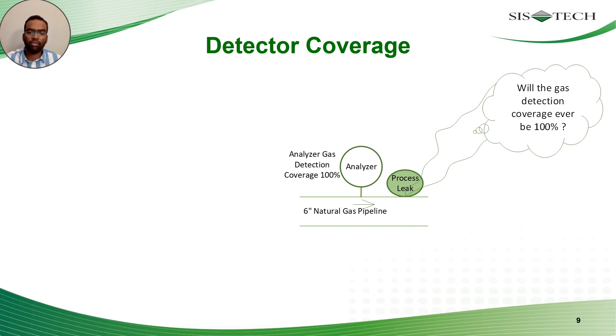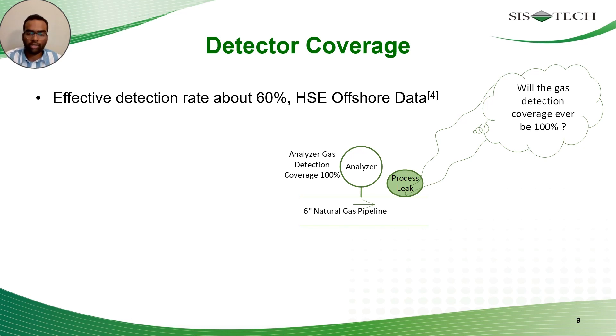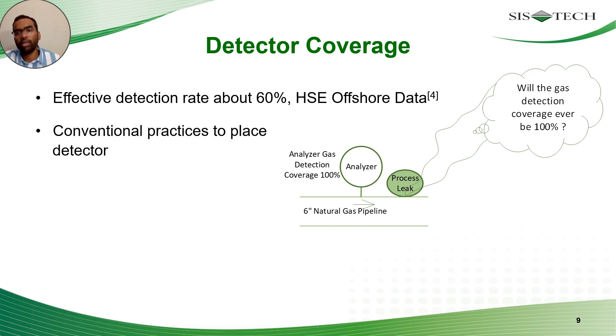Detector coverage is critical to overall FGS effectiveness. An analysis done by HSE on hydrocarbon release data showed that irrespective of the type of FGS design, the effective detection rate was about 60%. There are conventional practices carried out to place detectors — often based on experience or similar existing facility arrangements. However, there are many influencing factors: the nature of the release, environmental conditions, size and shape of the process area, presence of ignition sources, and the acceptable exposure limit for toxic releases.